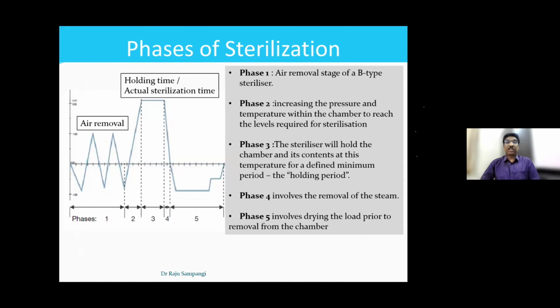So coming to the phases of the sterilization, the first phase would be the stage of air removal that we would see in a class B autoclave. Then is phase 2, wherein there is increasing pressure and temperature before we reach the holding time of the sterilization temperature. Once you reach the sterilization temperature, you have to maintain at that temperature for some particular time. That is called the holding time. And once you finish that, then you again involve removal of the steam, and then the drying happens.